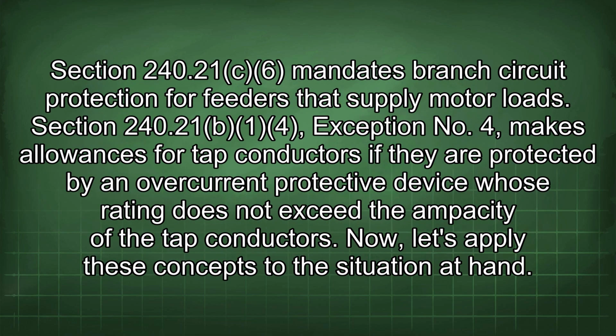Section 240.21(C)(6) mandates branch circuit protection for feeders that supply motor loads. Section 240.21, exception no. 4, makes allowances for tap conductors if they are protected by an overcurrent protective device whose rating does not exceed the ampacity of the tap conductors.